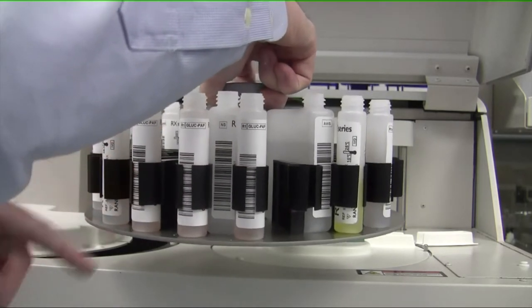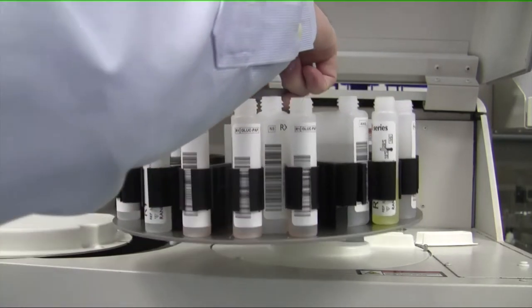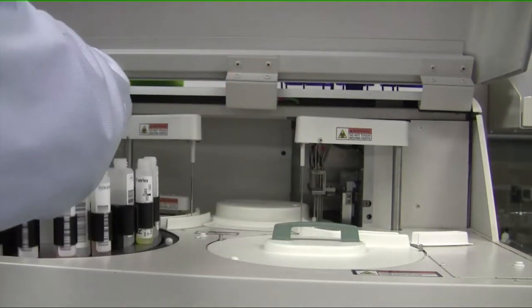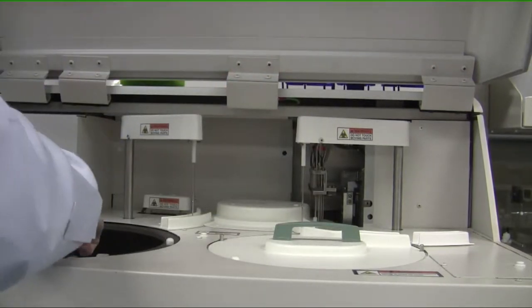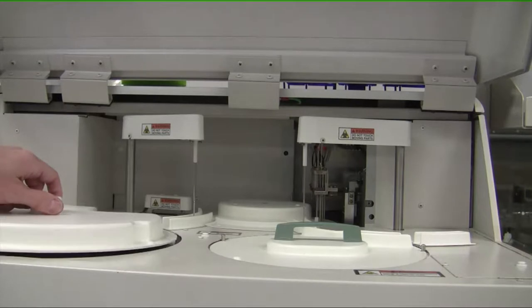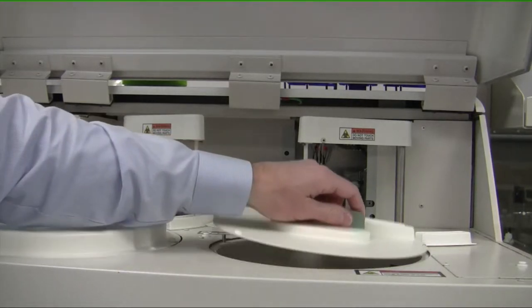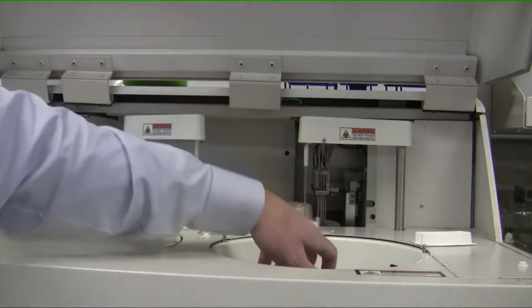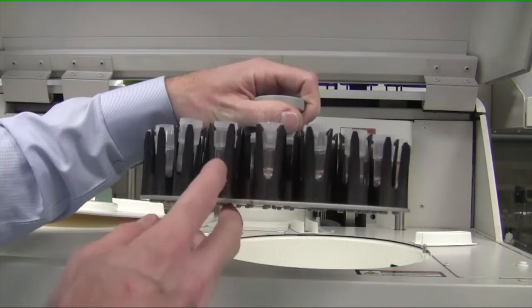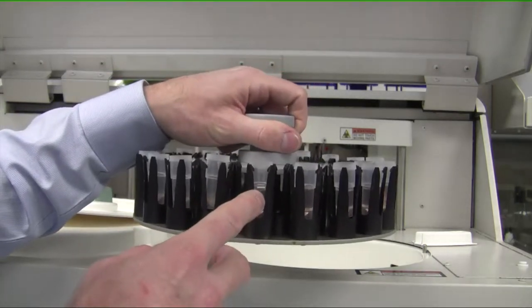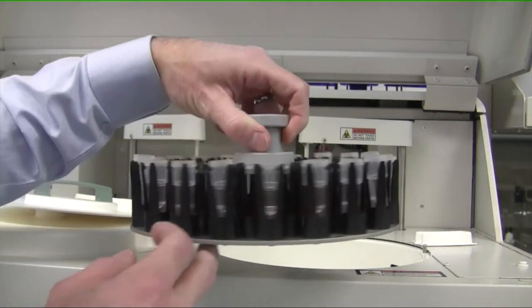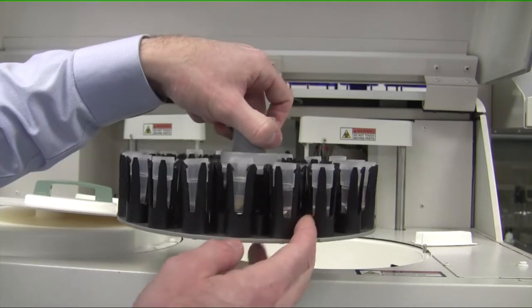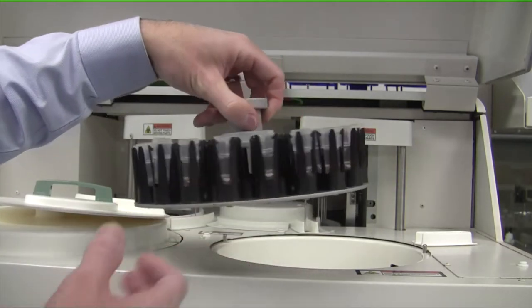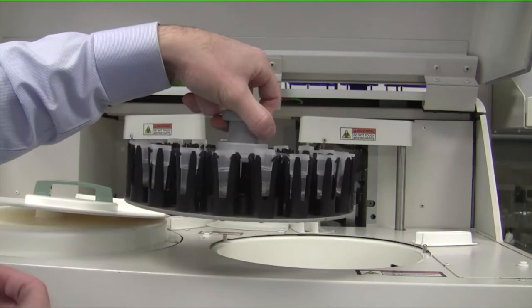And they're barcoded. And we just place the barcode out. And when we put it into the chamber, with a click of a button, the instrument will automatically recognize what reagents are on board. Over here are the samples. You put your samples into standard sample cups. Various instruments have various sizes, mostly depending on the throughput, but they also have different numbers of samples.